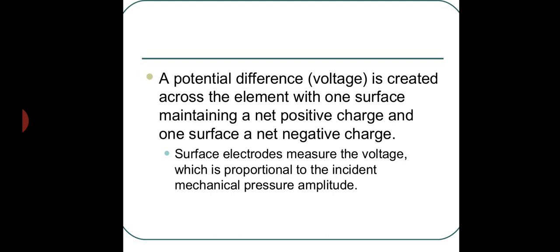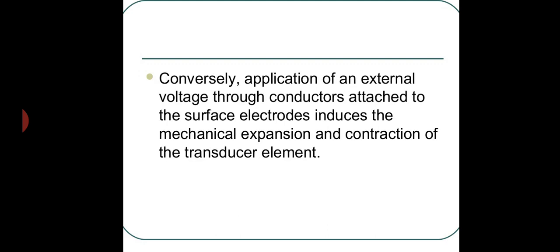Surface electrodes measure the voltage, which is proportional to the incident mechanical pressure amplitude. Conversely, application of an external voltage through conductors attached to the surface electrodes induces the mechanical expansion and contraction of the transducer element.